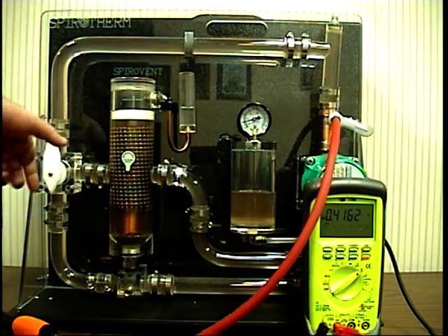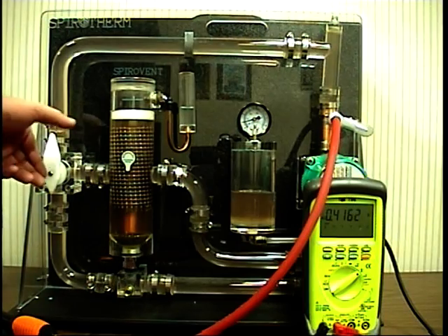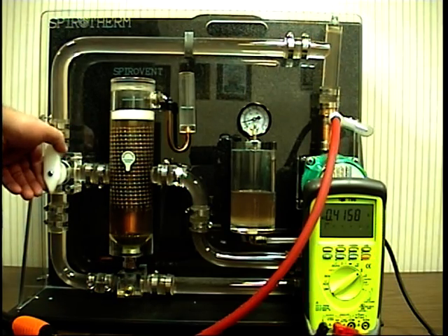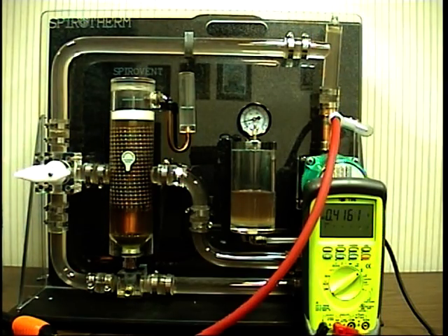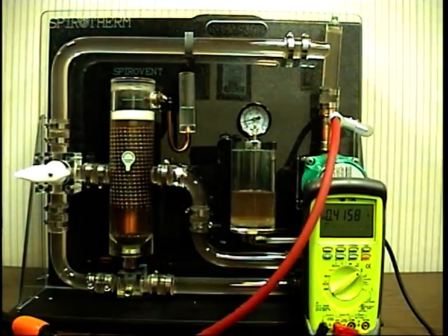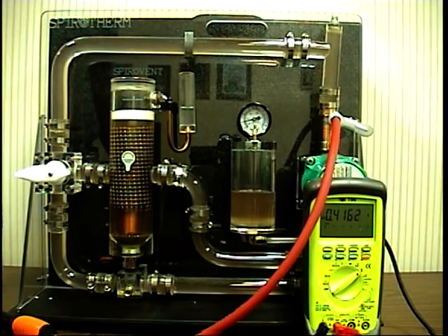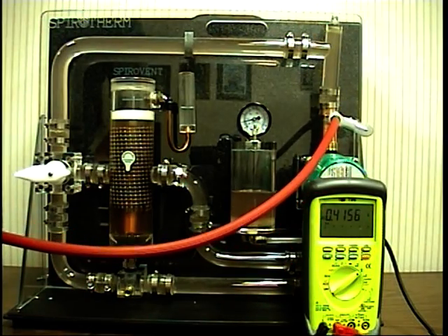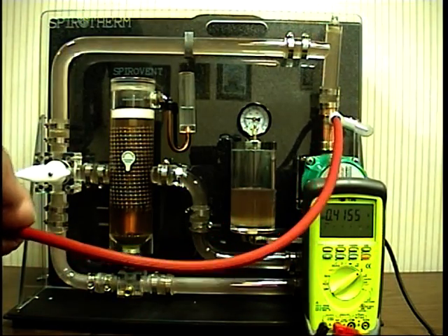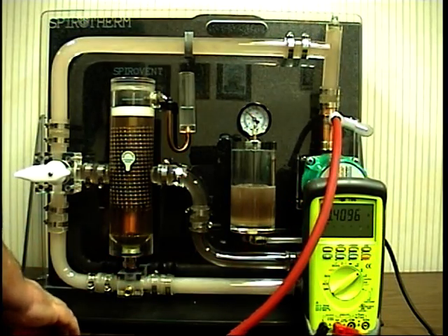Basically, we're going through the Spirotherm. Initial startup, I've very well got most of the air out of the system, as far as the free air and the entrained air. We'll go ahead and shut off the bypass. And we can also notice your amp draw on the system, a little bit higher with the glycol system than it was with the water system. Okay, so basically we'll go ahead and pump about the same amount of air. It was basically one pump full of air.